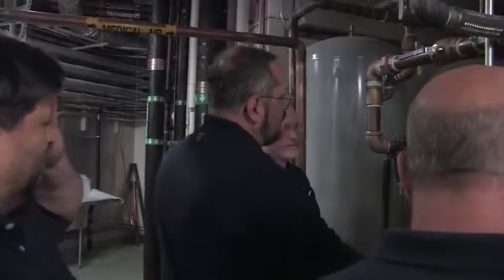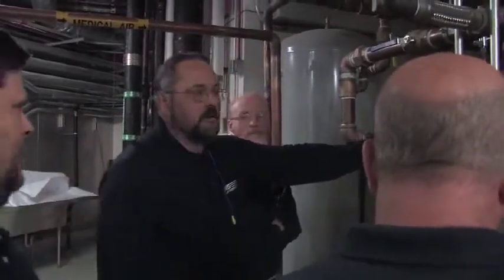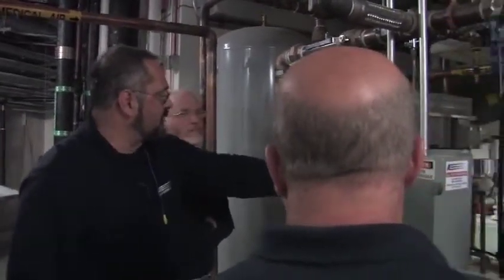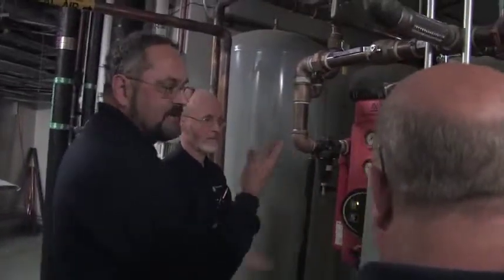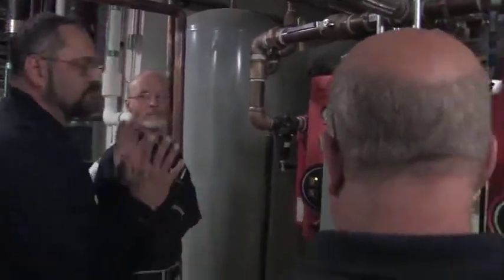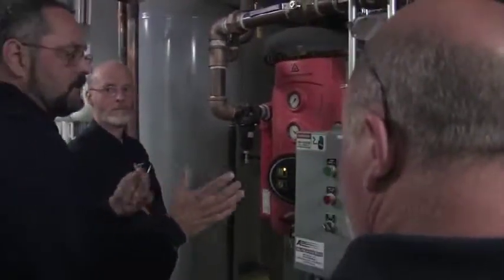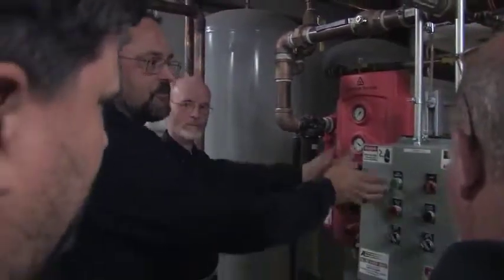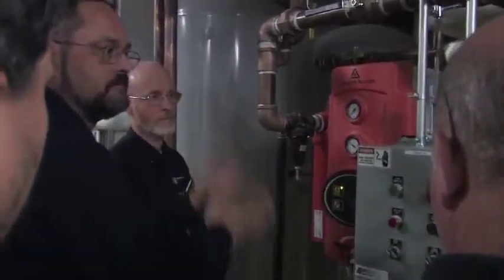So now you notice it's switched. Now we're on the other tower. This one's pressurized, the other one's purging. And that's exactly, if you ever suspect the dew point's bad, put it in this mode. Take the purge saver off and just let them cycle back and forth.